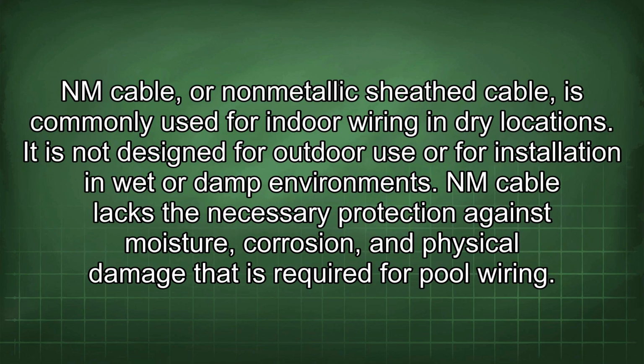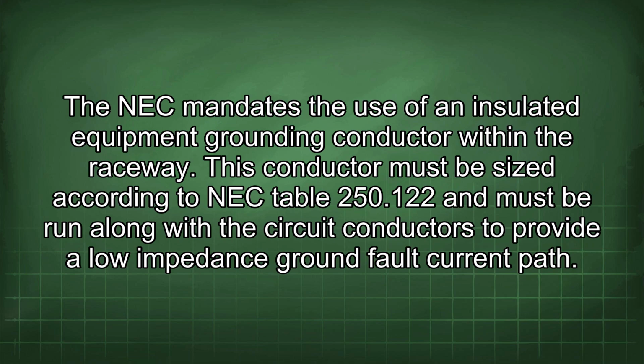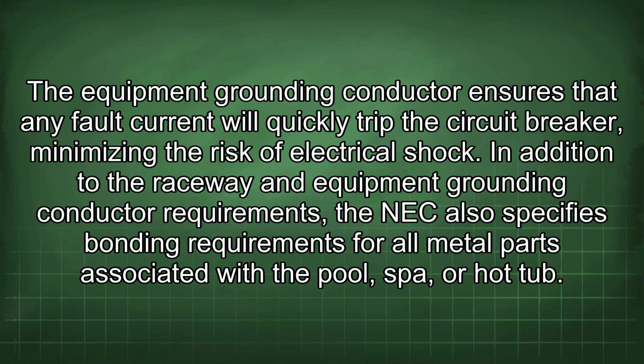NM cable, or non-metallic sheath cable, is commonly used for indoor wiring in dry locations. It is not designed for outdoor use or for installation in wet or damp environments. NM cable lacks the necessary protection against moisture, corrosion, and physical damage that is required for pool wiring. The NEC mandates the use of an insulated equipment grounding conductor within the raceway. This conductor must be sized according to NEC Table 250.122 and must be run along with the circuit conductors to provide a low-impedance ground fault current path.